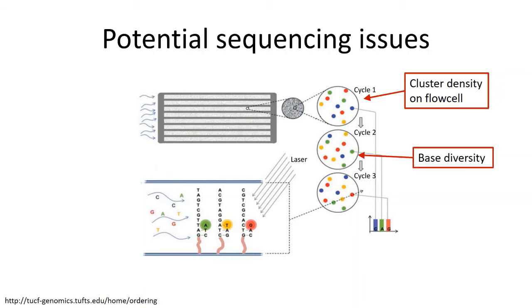Base diversity is also something that's incredibly important for the Illumina machine to correctly calibrate how it's doing its laser excitation and image settings and image analysis in order to correctly identify clusters. So for example, if many, many of the clusters on this flow cell have an adenine at the second position in this read, then the slide is going to be radiating green and there's not going to be good signal to noise calibration for what should be a fairly even distribution of nucleotides.